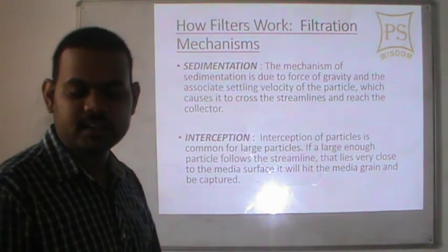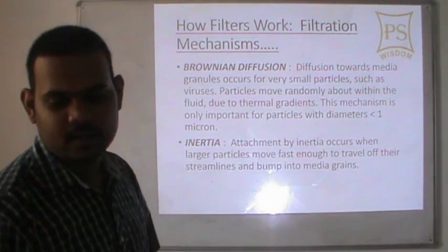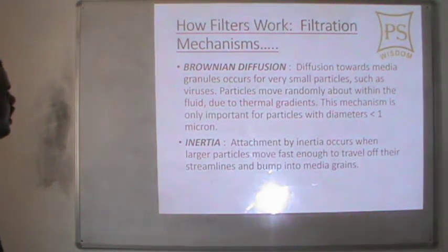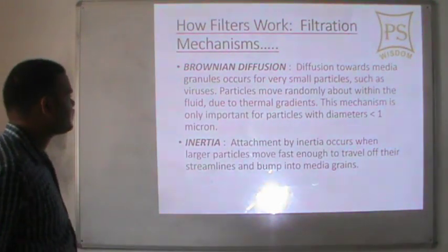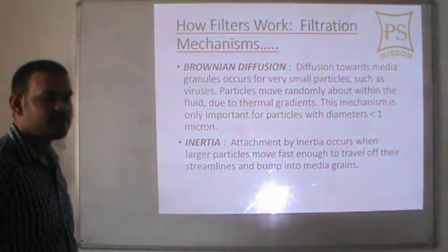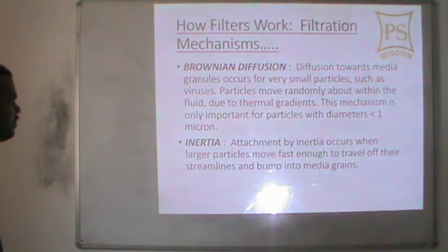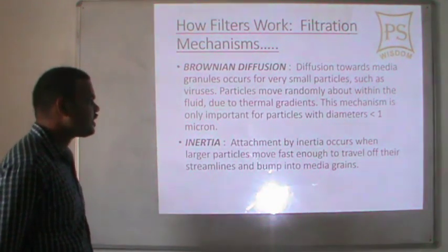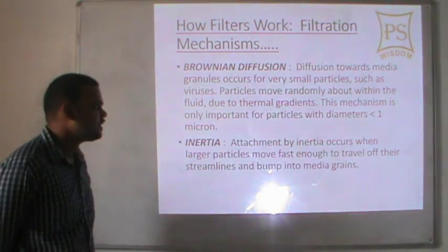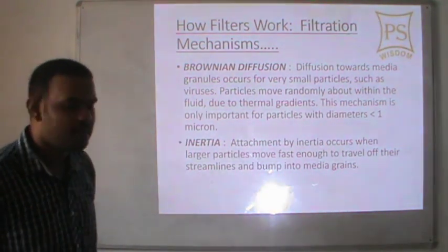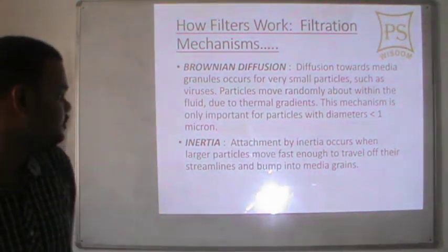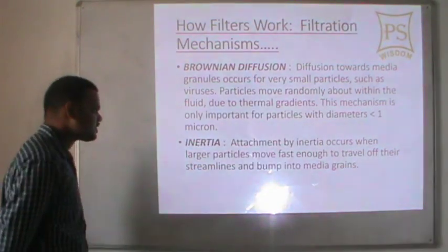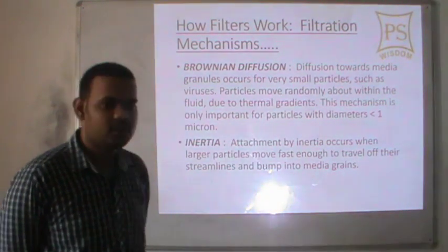The particle gets captured in the space between media grains. The third mechanism is Brownian diffusion: diffusion towards the media occurs for small particles such as viruses. These particles move randomly within the fluid due to thermal gradients. This mechanism is only important for particles with a diameter less than one micron.